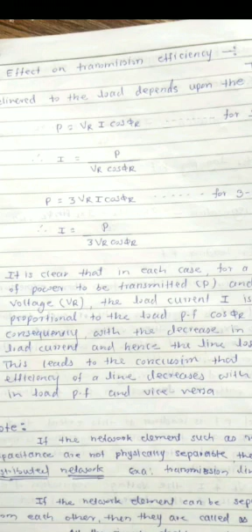So it is clear that for a given amount of power to be transmitted and receiving end voltage, the load current I is inversely proportional to the load power factor cos phi R. Consequently, with a decrease in load power factor, the load current and hence the line losses increase. This leads to the conclusion that transmission efficiency of the line decreases with a decrease in load power factor, and vice versa.